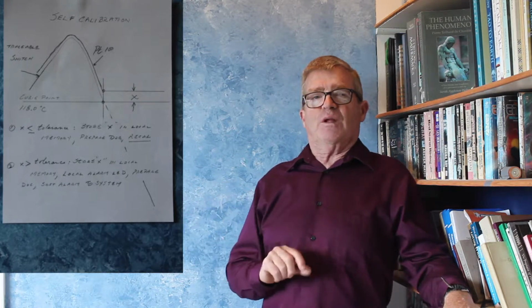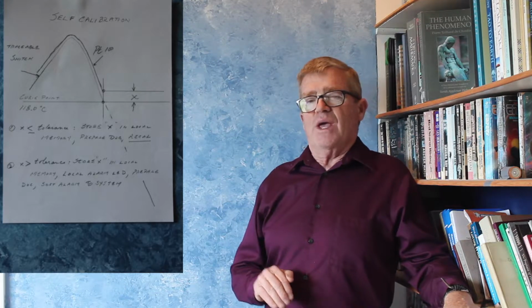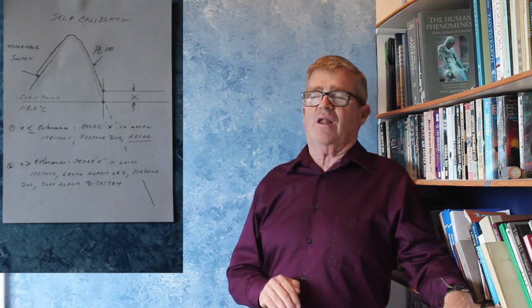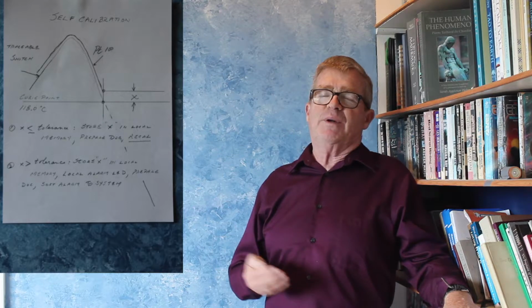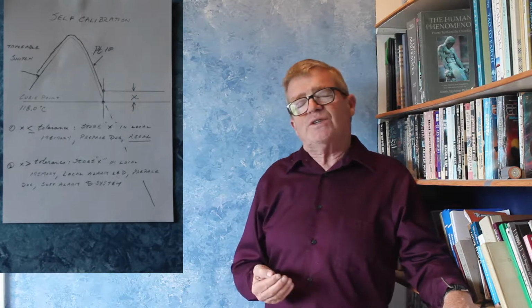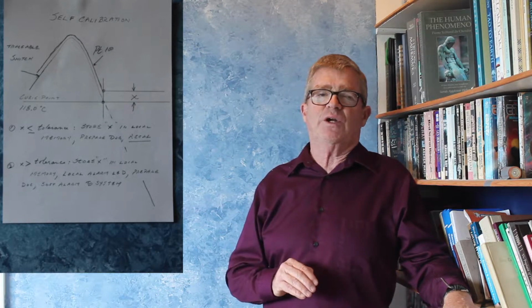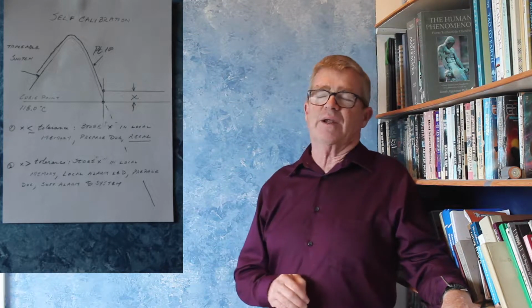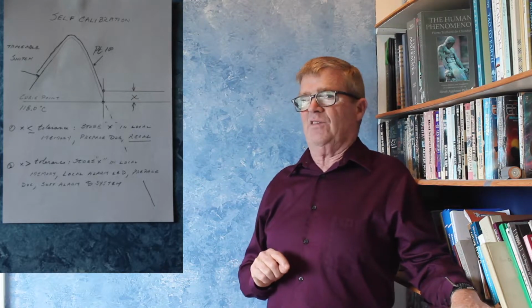If the difference is below tolerance, you're good to go. If the difference is above your tolerance, you're still good to go, but it will notify the system, we just had an out of tolerance in the PT100. It's already been recalibrated. Now that's the essence of this instrument. Every time this device passes through the Curie point in either direction, you recalibrate. You also save the documentation from that calibration activity, so it can be downloaded later.